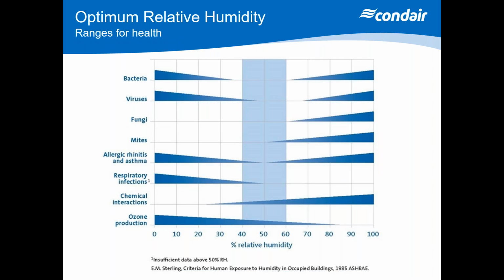Now, a nice way to illustrate this is this diagram that you've probably seen before. It's the Sterling criteria for human exposure to humidity in occupied buildings, and it's straight out of the ASHRAE handbook. This shows the proliferation of airborne pathogens, bacteria, viruses, fungi, mites, allergic rhinitis, respiratory infections, chemical interactions, and ozone production at different levels of relative humidity, starting at 0 and going up to 100. If you take viruses, for instance, there's a high proliferation at 0, and then it tapers down and drops away. There's a sweet spot between 40 and 60 before we start to see it increase at the higher levels of relative humidity. So it is really between 40 and 60 that we're looking to maintain our environment.